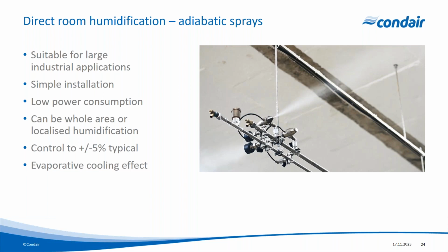And of course, one of the other benefits of doing this is that we get evaporative cooling. So we mentioned that as the water evaporates, it's sucking heat energy out of the air. Well, we can utilize that. We can use it for cooling a large area, because for every litre of water that you're evaporating, that is going to suck 680 watt-hours of heat energy out of the air. So you can also get a significant amount of cooling out of a system such as this.